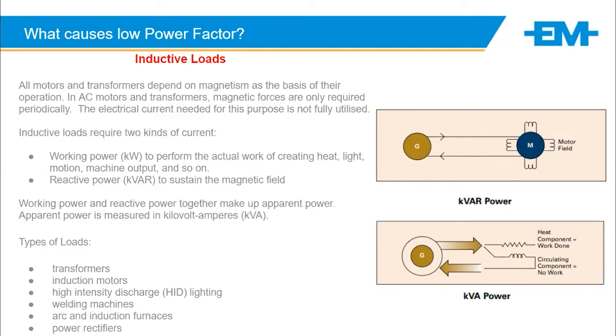So quite often that happens here, depending on the size of the consumer, they get what we call a maximum demand charge, which could be a type of penalty charge or additional unit charge. So one penalty because you exceeded your demand, your kVA, which is allowed to your site, and then another charge for the units over that.